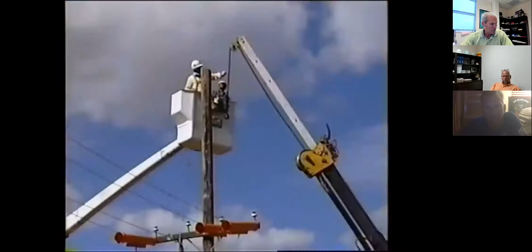An alternate method to chunking is the single section method, referring to removing the top of the pole in one large piece. The bucket and line truck are stabilized at safe distances from each other with the pole easily accessible from either truck. The boom of the line truck is placed near the top of the pole where the single section will be removed. The two employees in the bucket take a sling up and attach it near the top of the pole utilizing a choker attachment.